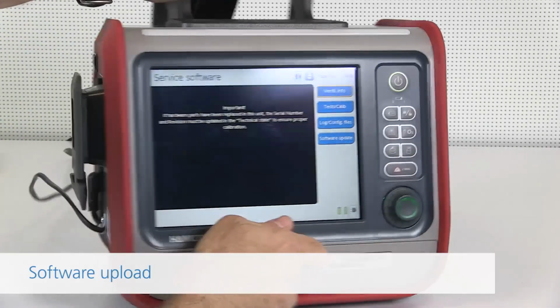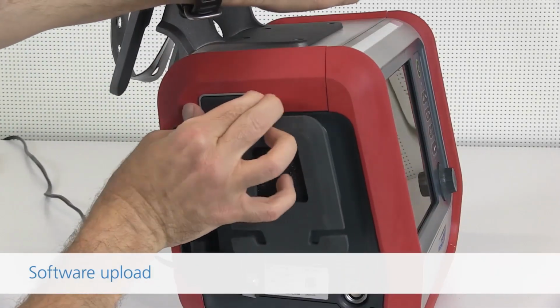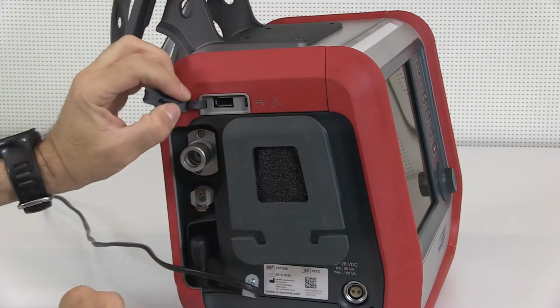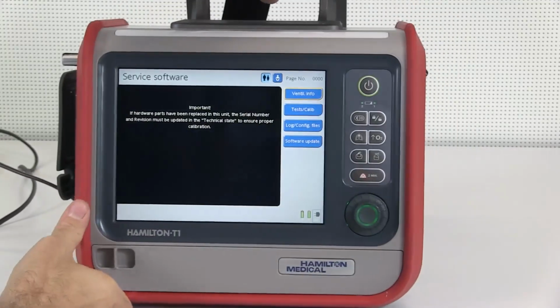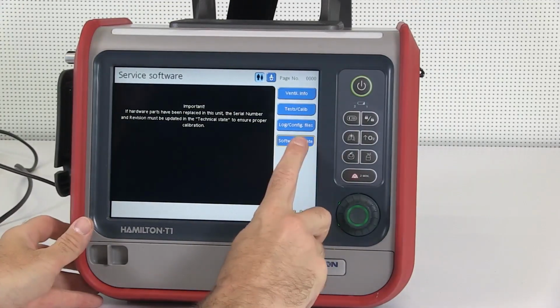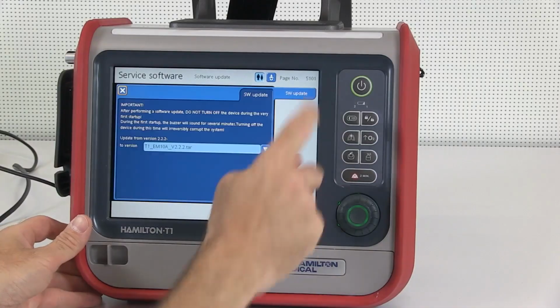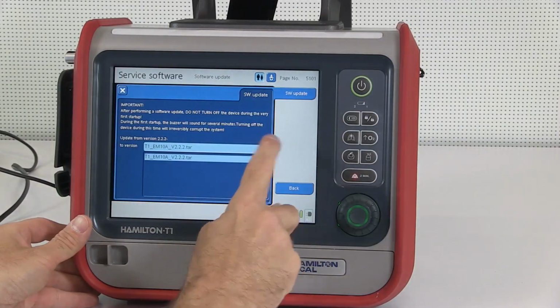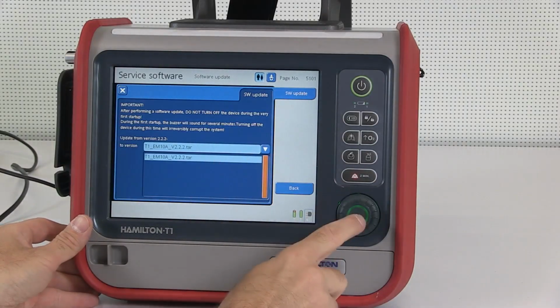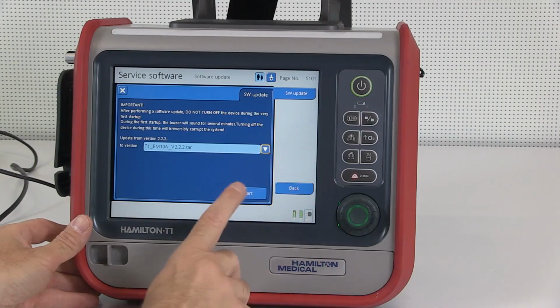Download the latest software from the PartnerNet on the Hamilton Medical website. Start up the ventilator unit in service software mode. Insert the USB flash drive into the USB port. Touch Software Update and then Software Update again. Choose the appropriate software version tar file to install and touch Start.